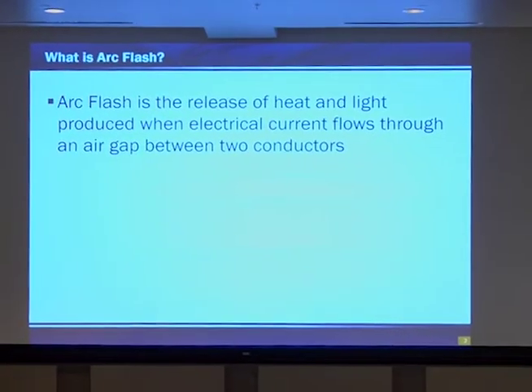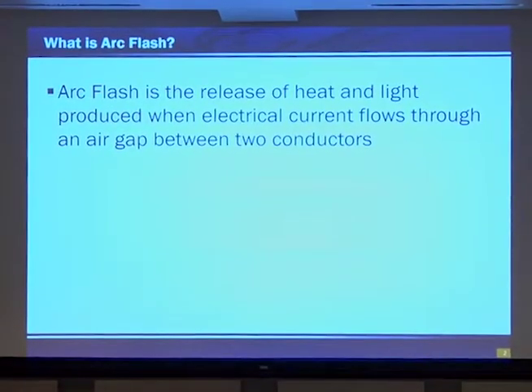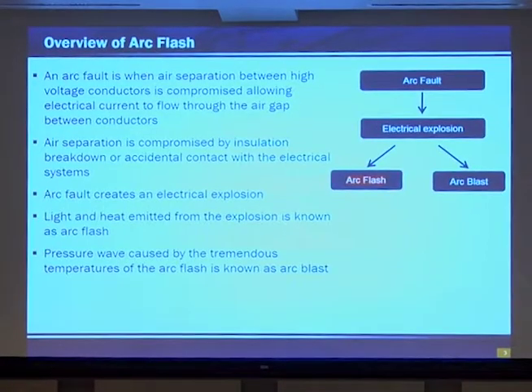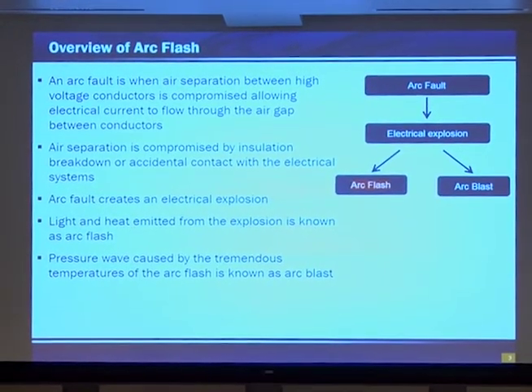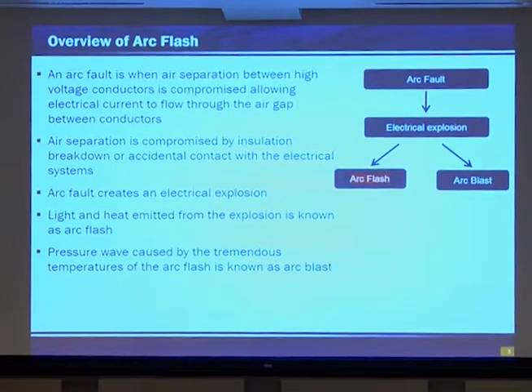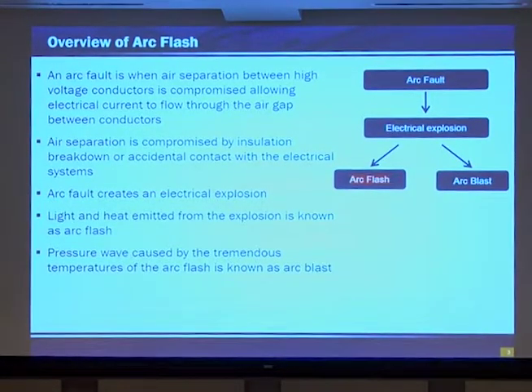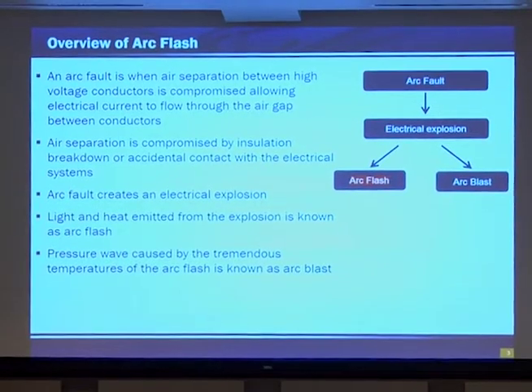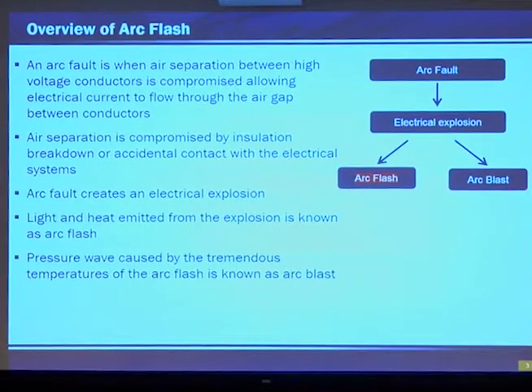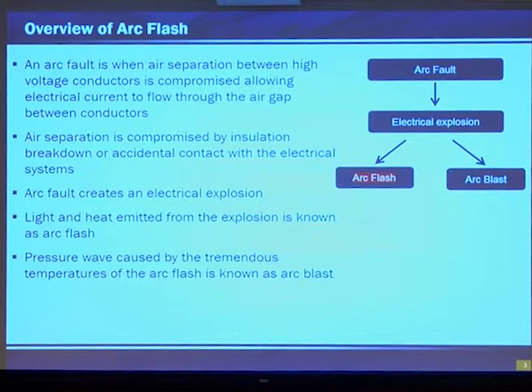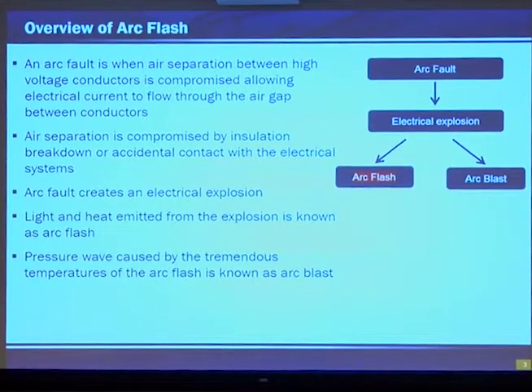So let's first start off with the definition of arc flash. Arc flash is a release of heat and light produced when electrical current flows through an air gap between two conductors. Let's look at the structure of an arc flash. The first thing to happen is an arc fault. An arc fault is when the air gap between two high voltage conductors is compromised, allowing an arc to form, creating an electrical explosion. That electrical explosion is made up of two things, an arc flash and an arc blast. The release of heat and light is what's known as an arc flash. The release of high pressure waves is what's known as an arc blast.